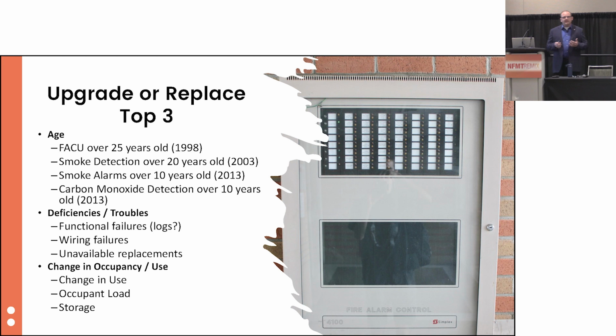In general, manufacturers of fire alarm systems create their systems to last 20 to 30 years - that's the general lifespan of a major manufacturer's fire alarm system. So if you have a fire alarm system installed before 1998, it's time to create a plan to look at that system and either upgrade or replace it based on the equipment you have. That 25-year rule is a very solid rule, largely because of major technology shifts, which we'll see in our presentation.